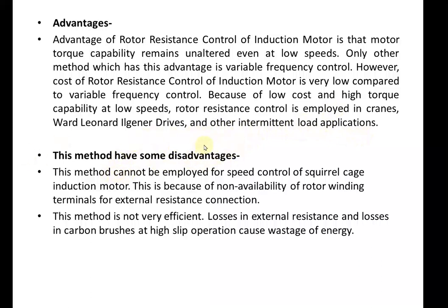The disadvantages of rotor resistance control: this method cannot be employed for speed control of squirrel cage induction motors because there is no provision of supply to the rotor — the rotor winding terminals are not available for external resistance connection. It is only applicable for slip ring induction motors. Also, this method is not very efficient — there are losses in the external resistances and in the carbon brushes, especially at high slip operations, causing a wastage of energy. It consumes and wastes more energy than the VFD control.